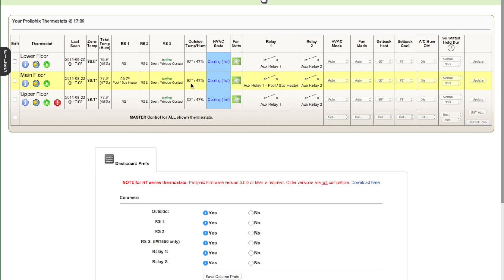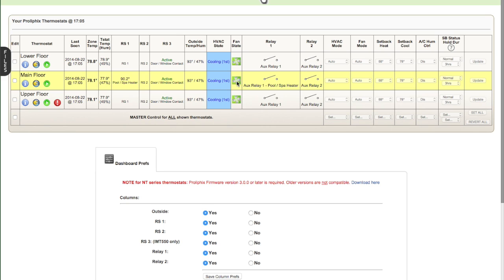Then after the remote sensors, we have the outside conditions. So this just gives you an idea of what the conditions are outside. We see here in this column, HVAC state, that all three of them are running cooling first stage. I'm not sure if these are dual stage systems, but if they were, and it was cooling both stages, it would indicate as such. So you'd see a slightly darker blue, and it would say first and second stage cooling. We see that the fans are running, which you'd expect when it's cooling.